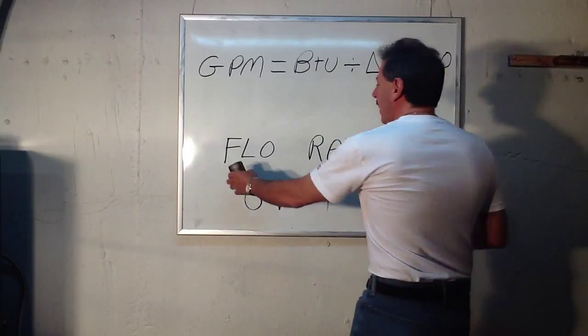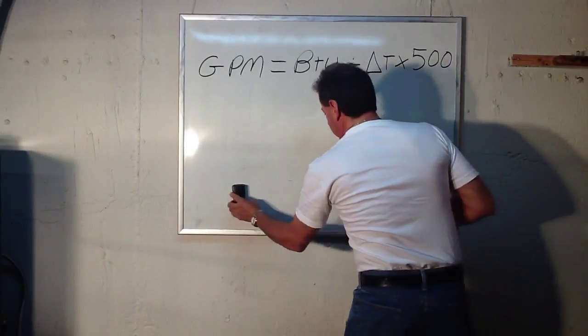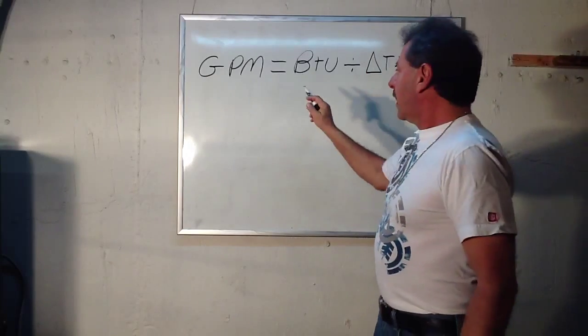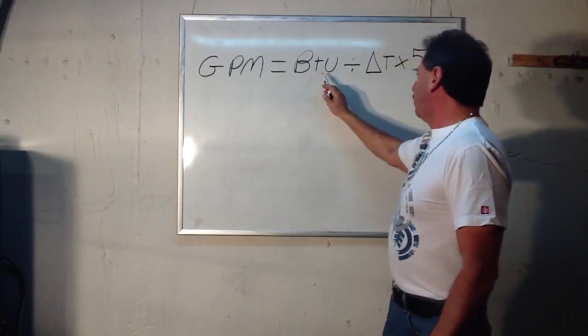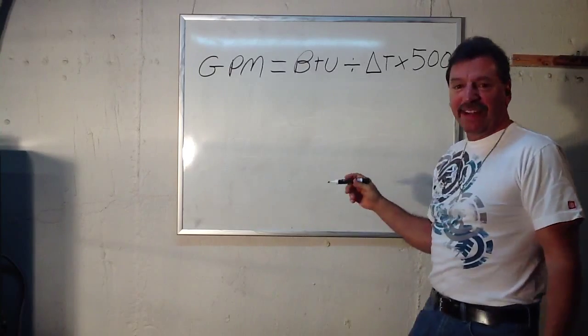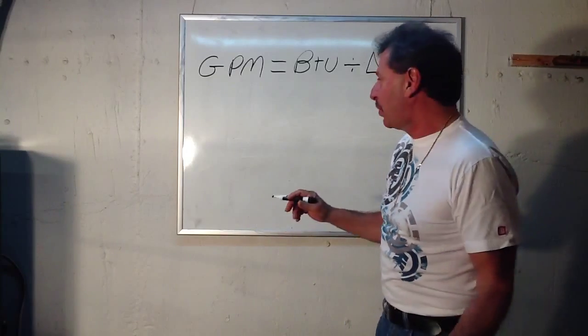That's what we're going to find. And there's a simple math equation that'll do that. Gallons per minute equals BTUs divided by the delta T times 500. I know it sounds like a boatload of information, but I can promise you it's pretty easy.